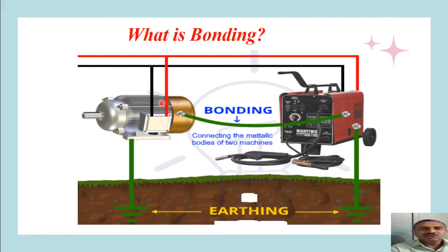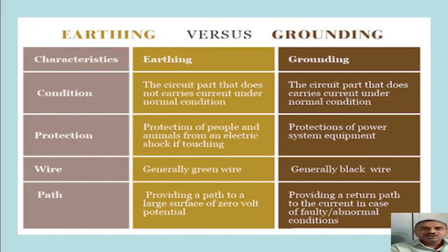You can see that on the same supply system, a motor on one side and the controller associated with it are operating, and by making the bonding of these two bodies of equipment, we are making their voltage to be held at the same potential, and that is the potential of earth, which we are assuming as the 0 potential. Now let us see the difference between earthing and grounding in the context of Indian scenario. We are comparing them on the basis of characteristics.